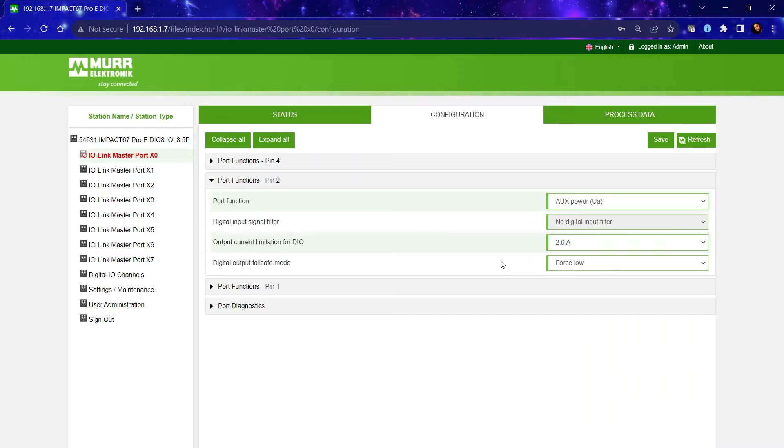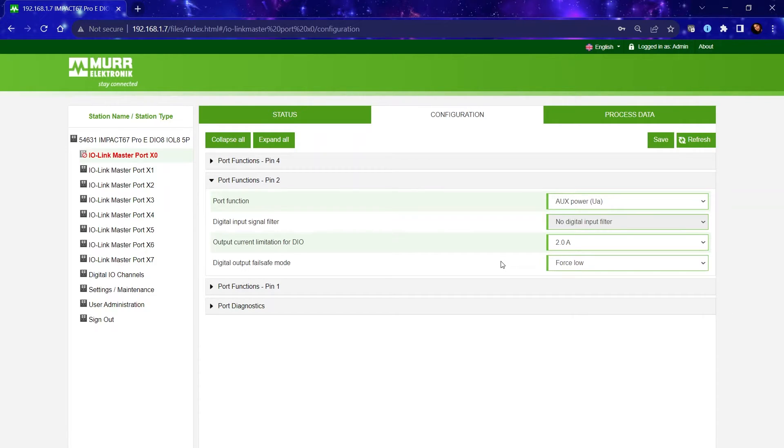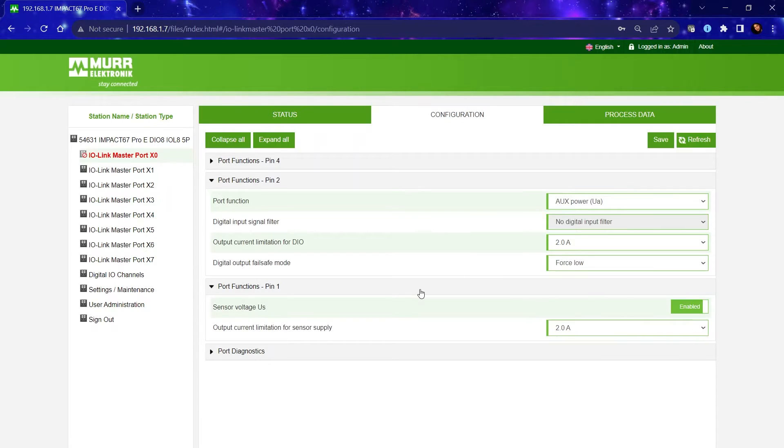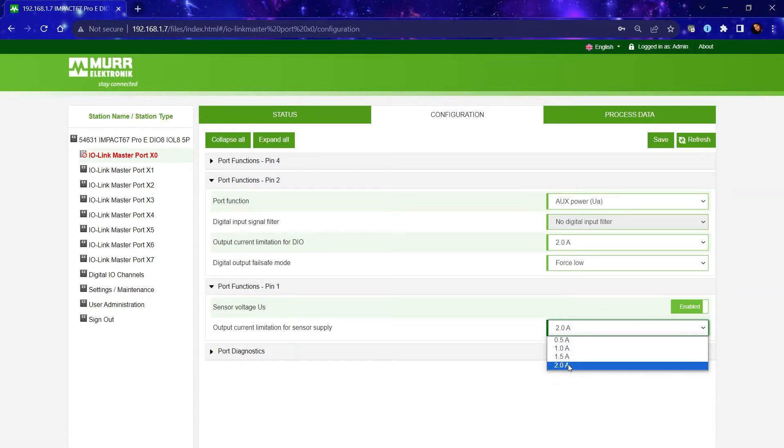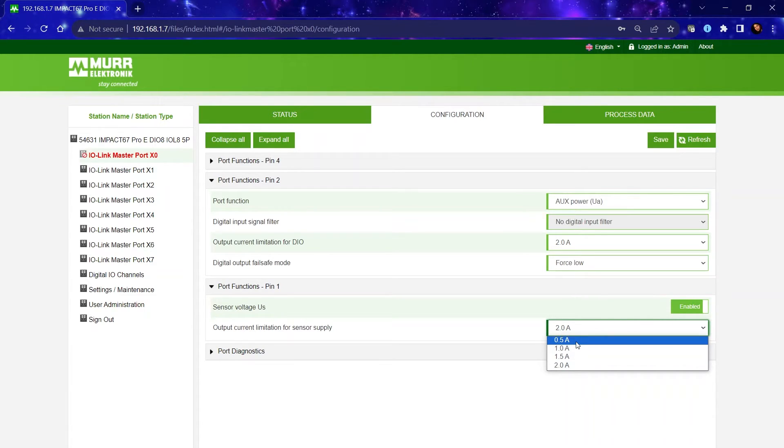Another way that this would benefit you as a user is it increases the selection of IO devices and it doesn't limit you based on the current consumption. For example, there are IO-Link devices in the market that require more than half an amp just to power it up. With our block on the pin 1, you can change that with a click of a button instead of having to get creative with a T-coupler and an extra power source.